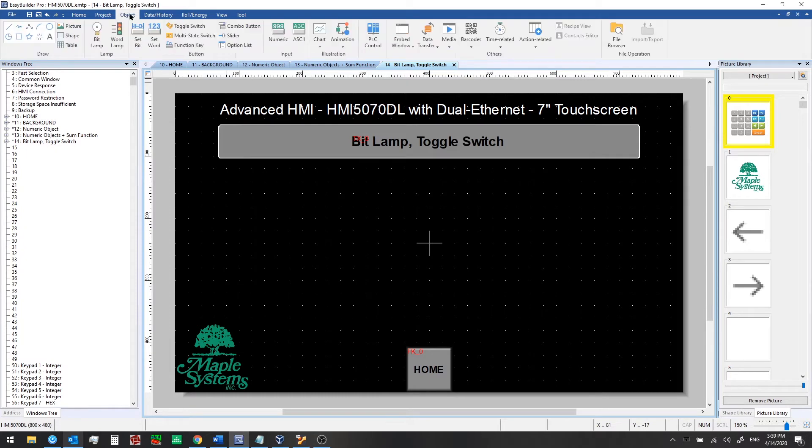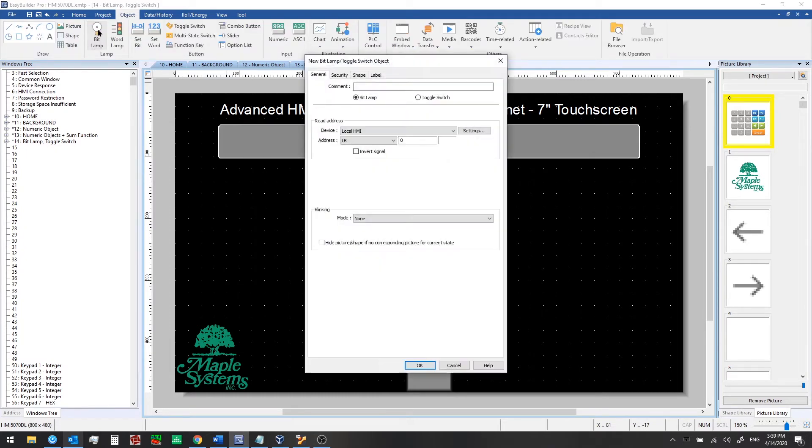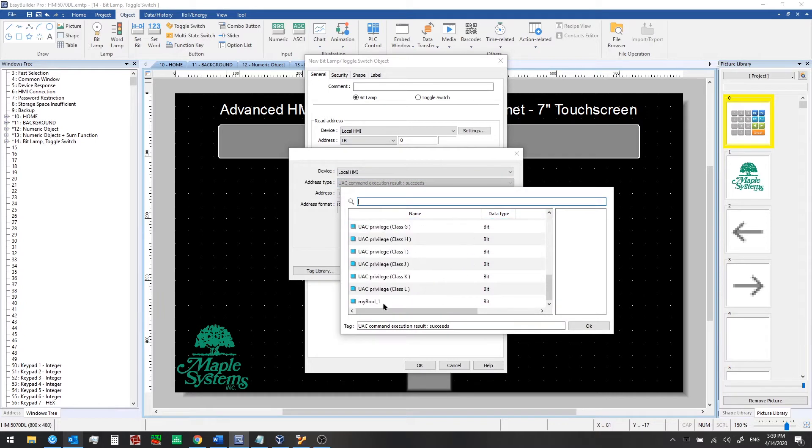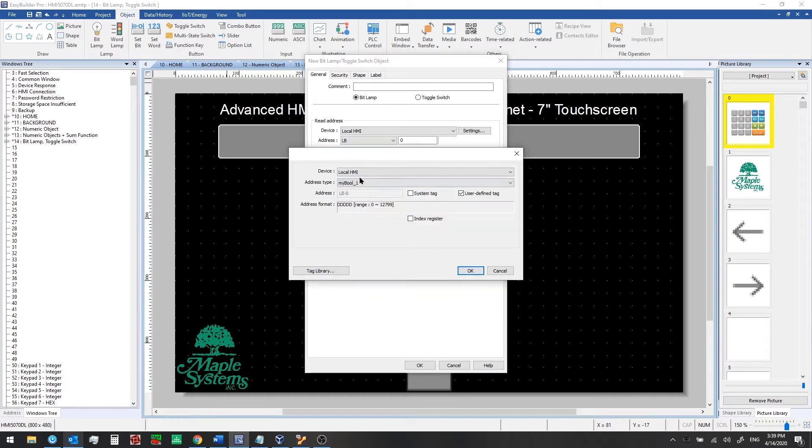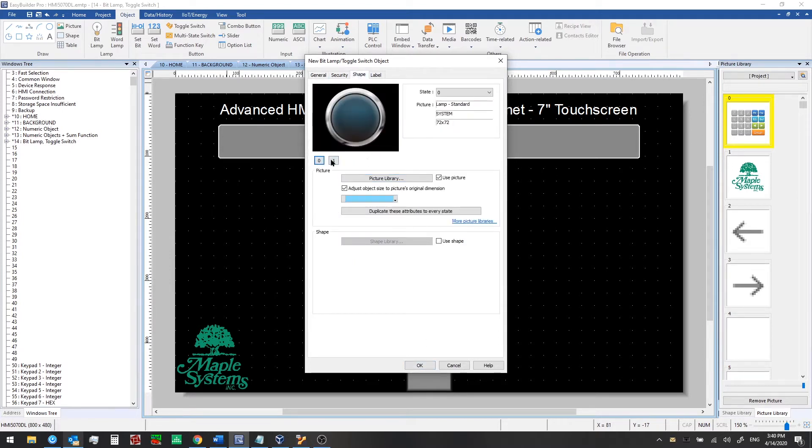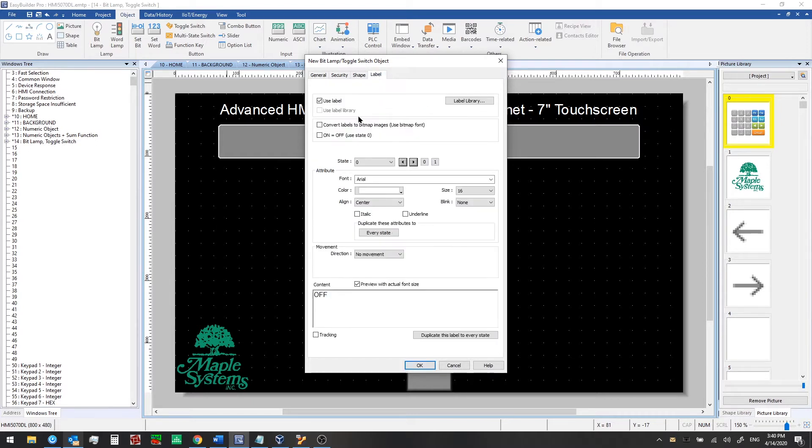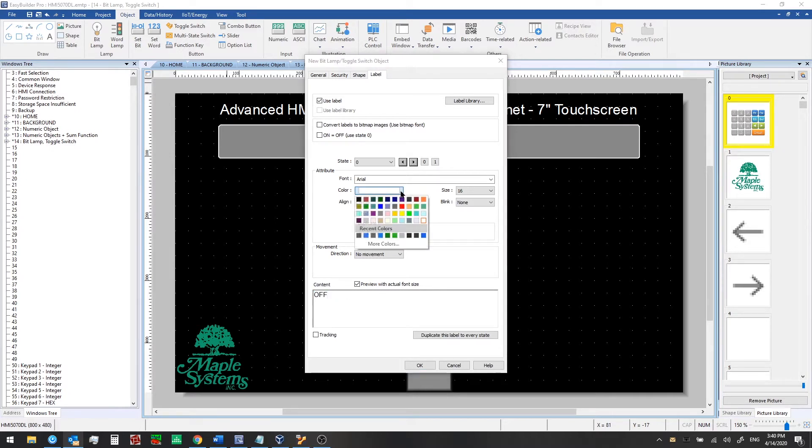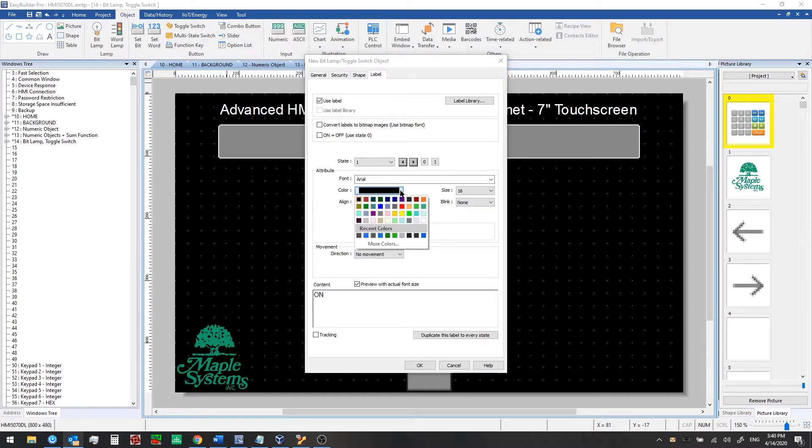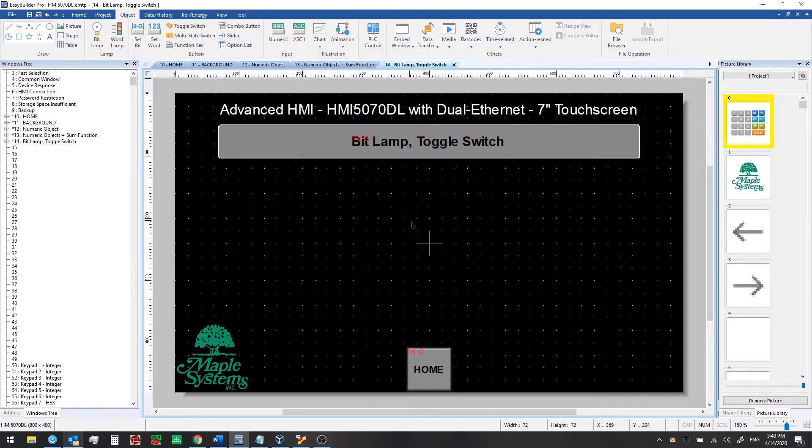Now we'll go to the object tab and we're going to select bit lamp first. Click on settings for the read address. Note that we have bit lamp selected here. We'll show you toggle switch in just a moment. Click on the settings button here, click user defined tags. Then you can select your new user defined tag. Click OK and go over to the shape tab. So you can get an idea of what it will look like when it's off and on. And we'll go to the label tab and add a label. So in the off state, it will have white text, Arial, size 16. If you click on this one, you'll see the next state. So the second state will have the word on with black text.